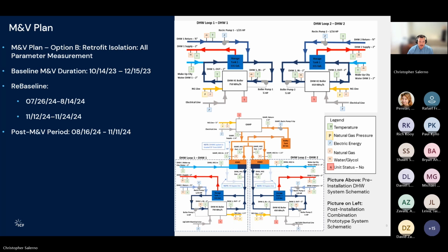And here's a legend to show all the M&V points that were used in this system to capture the net heat output. What I mean by that is the actual heat that is supplied by the boiler into the water out to the system. You can see here we have the green temperature sensors, and the orangish M dots. Those are the mass flow meters, the water flow meters that we use to capture the inline water flow, in order to calculate the heat energy coming into the system from the cold water, in from the recirculation load, and then out from the supply, which we call DHW supply, the hot water going to the tenants. So this is hot water going to one side of the property and the other side.